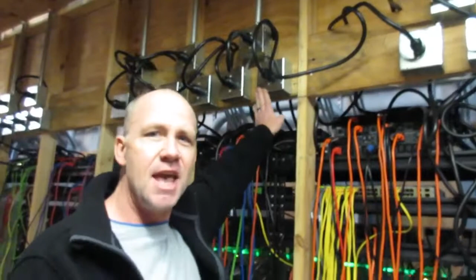Now, as we're seeing this, I want to show you the electrical connection. Each of these is a 30 amp circuit at 208 volts. We've got about 100 of them, so we can do about 500 kilowatts of electricity. Those come to a PDU, a power distribution unit, and then the miners are plugged into the power supplies, and then the miners.